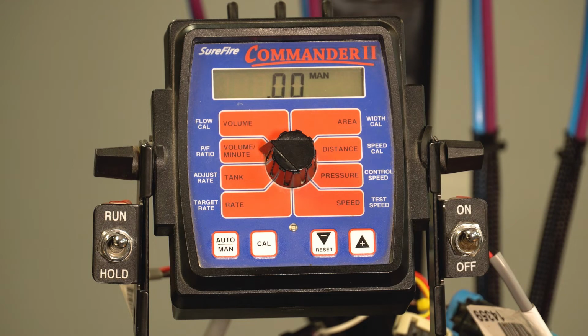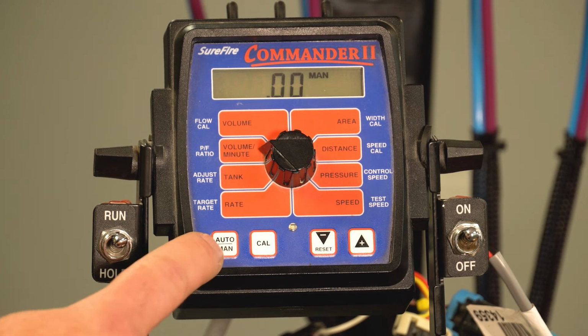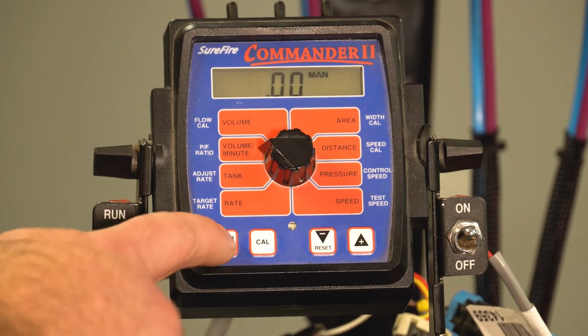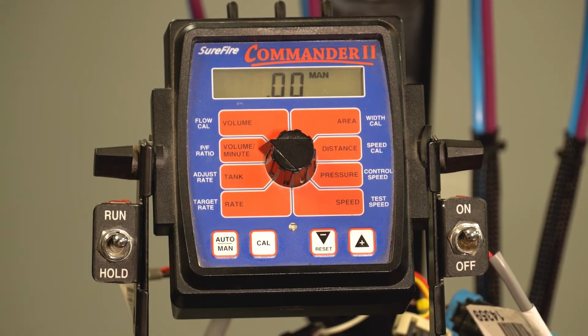Any of those kinds of things that you want to do, or just generally make sure that you have power and that the system is pumping. This is the way that we want to do that. So here in the bottom left is the auto man button. If you click on it, we'll go into auto mode or manual mode. So again, for this manual test, we want to be in manual mode.